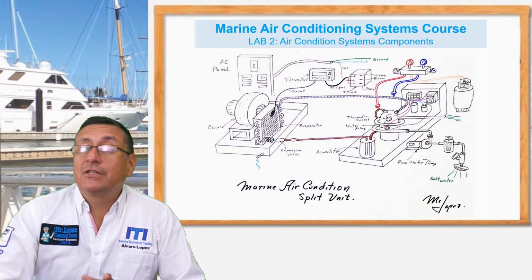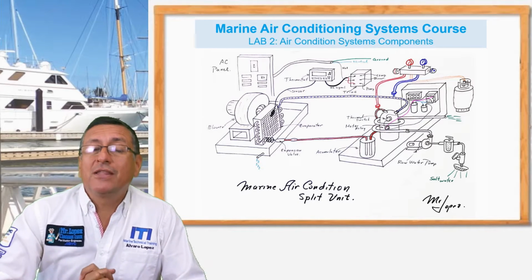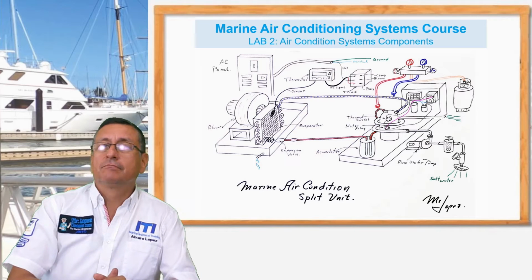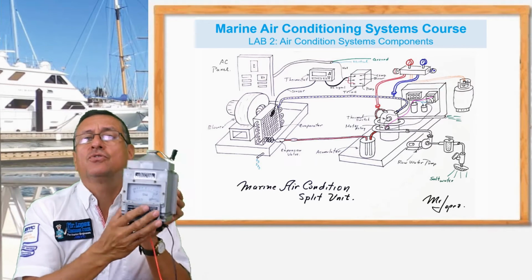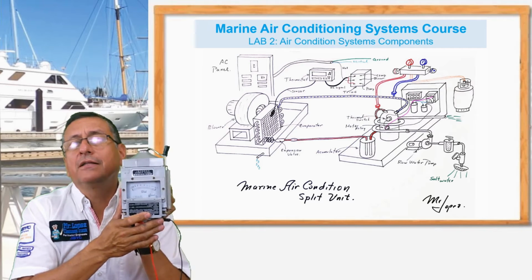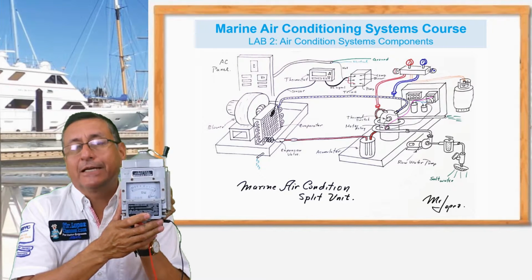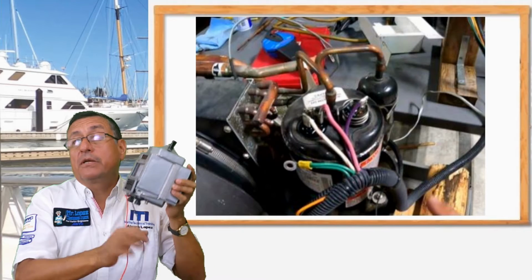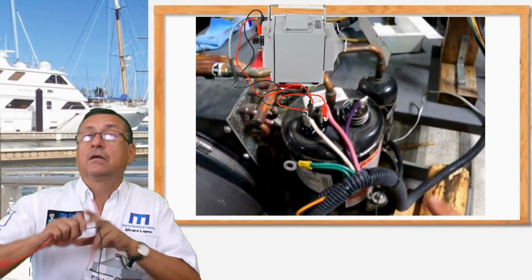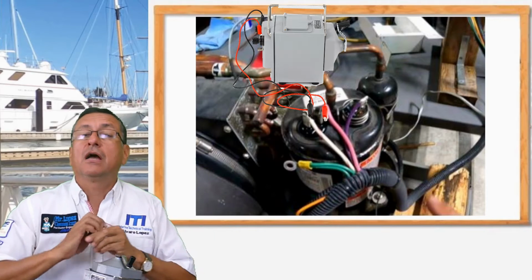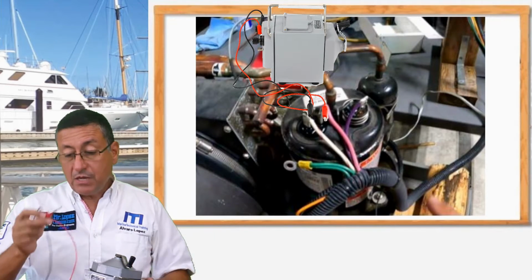This is an indication that the winding of the motor, the winding of the compressor, is not good. I need to use the megohmmeter. I need to use the megohmmeter to verify that situation. Yes. Okay, we are going to use the megohmmeter. Right now we have the start relay with the cables out, and we are going to check with the megohmmeter.